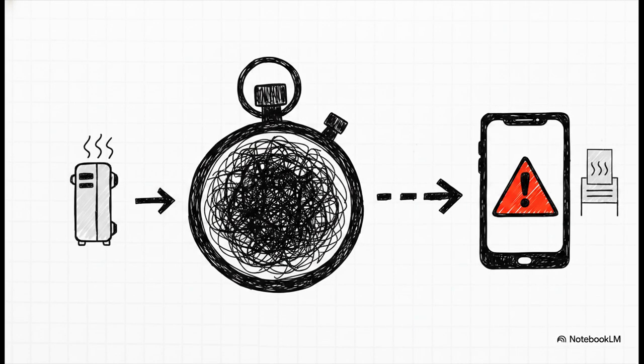Here's a slightly more advanced workflow, but it is an absolute lifesaver. You can pair your standard temperature control with duty cycle alerts. You set an alert to trigger when a heater's or chiller's duty cycle exceeds a safe threshold, meaning the equipment is running way longer than it normally should to reach its target temperature. This acts as a brilliant indirect early warning sign that your equipment is starting to fail, or maybe a window got left open, long before the actual temperature of your tank crashes.